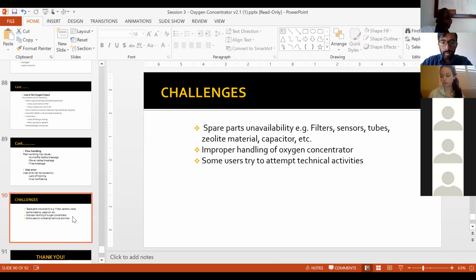But it depends on the country. I think I did mention earlier that you can buy zeolite, but whether you can send it to your country depends on how they agree with that. Logistics, I'm not sure, but I have experience doing this particular thing in a different country. We replaced that raw material. You open up and remove the old material, replace it with the new zeolite material, seal it properly, check the leakage line, and use it back. It works.